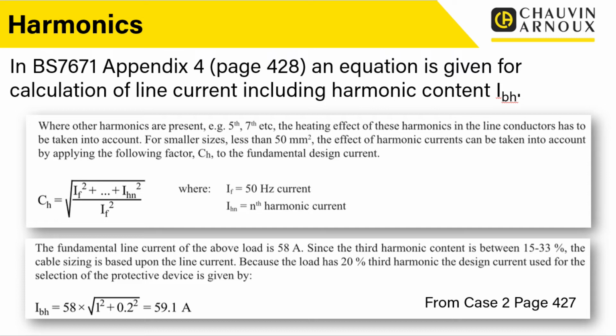Now, we'll talk about these in a little bit more detail in a moment, but in Appendix 4, they actually give us these cases. So they've got some worked examples, which are really useful to get an idea of what's going on. And in there, they give an example of working out IBH. They say the fundamental current of the above load, and they give some detail in the case study there, is 58 amps. And it says, since the third harmonic content is between, so in the example, they use 20% THD, so it's between 15 and 33.